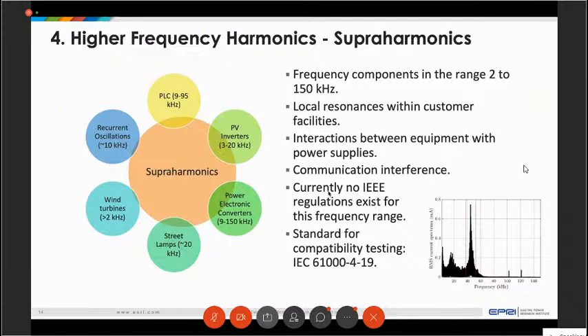So it has relatively good characteristics. They usually have relatively good characteristics for our traditional harmonics - the third, fifth, and seventh harmonic. They're controlled very well within the standards, but these devices have switching frequencies that might be 15 kilohertz, 20 kilohertz, or even 50 kilohertz.